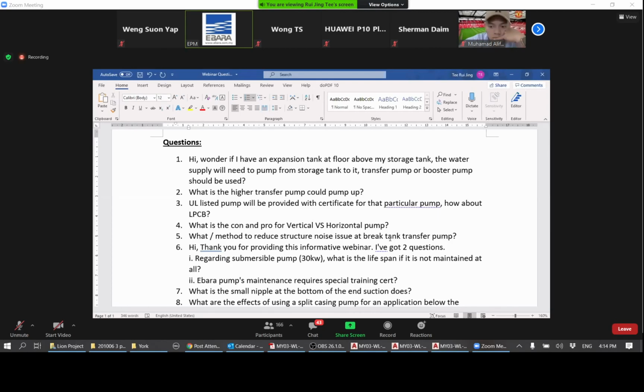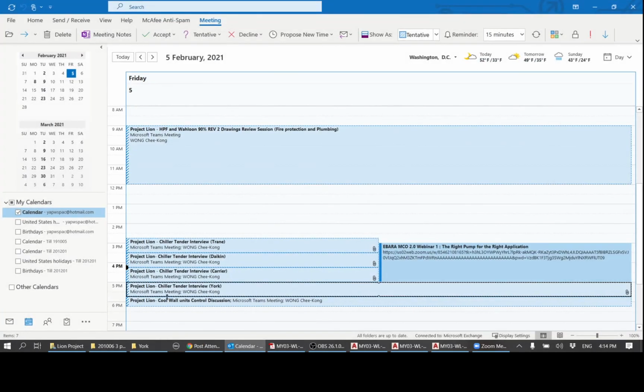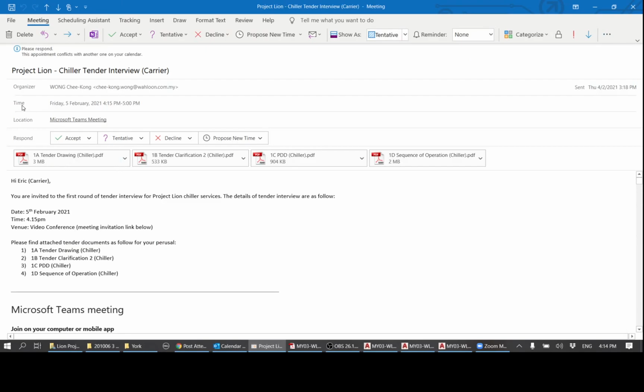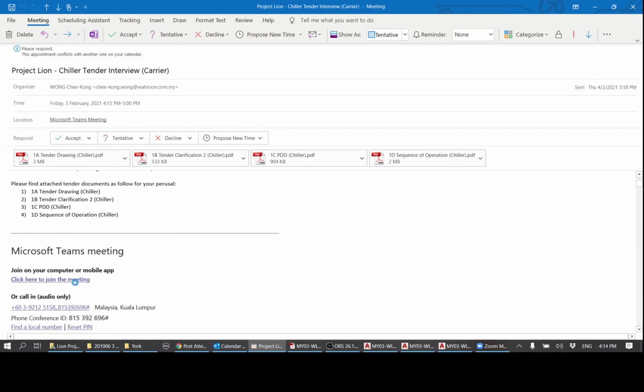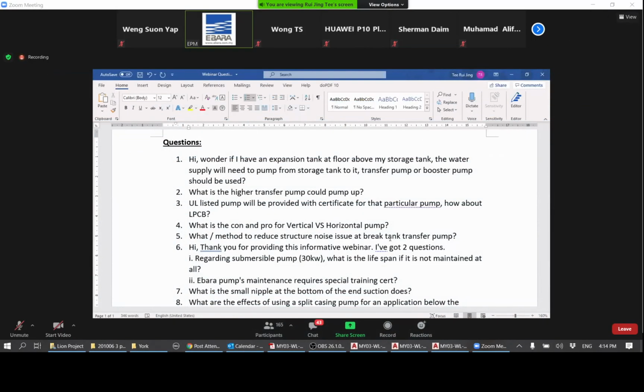Number 3: a UL listed pump will be provided with a certificate for that particular pump. How about LPCB? Here you are asking about our fire pump range. We have pumps that are compliant to the LPC standard. In fact, our GS series fire pumps comply with LPC, but they are not listed by the LPC board. So there's a difference between complying and listing. Complying is basically meeting the specifications of that particular standard. But listing means you have a certificate from a certain approval body that specifies that your pump is certified or has met that certification.